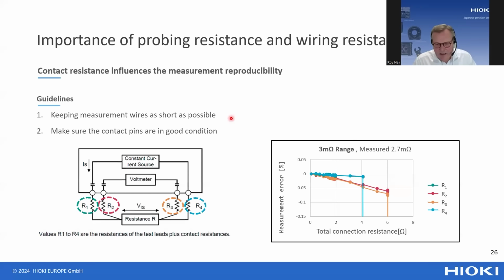There is a relationship between the total resistance of the connection wires and the internal resistance of the battery. The internal resistance is very small compared to the wiring resistance, which is quite high. In this graph on the right-hand side, you can see that when the connection resistance—for instance R3, the sense low wire—increases, meaning the resistance increases as the length of the cable or wire increases, it has an influence on the measurement error. In other words, this graph shows that when you want an accurate measurement, you should try to reduce the length of your measurement cable as much as possible.